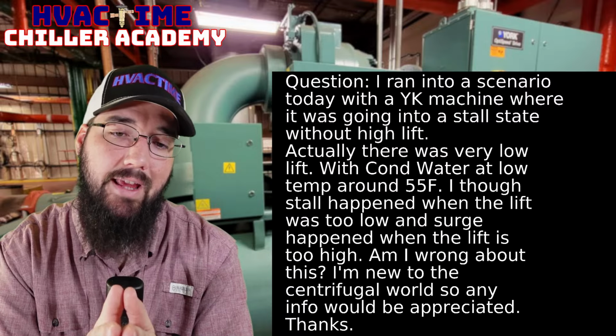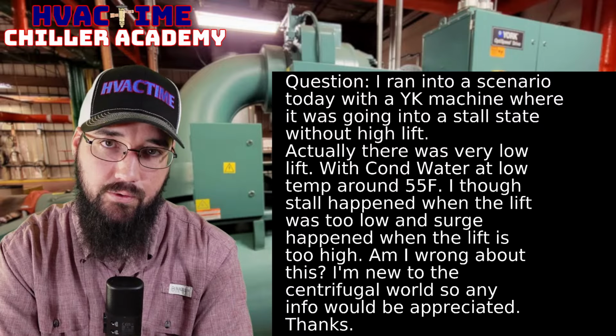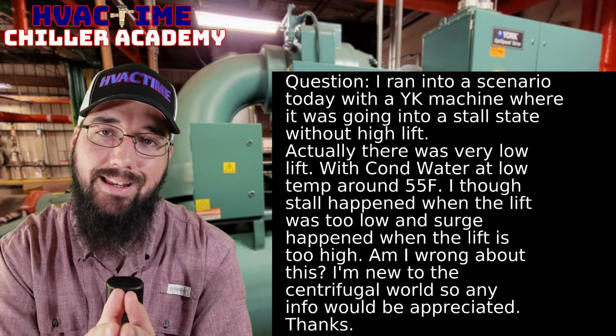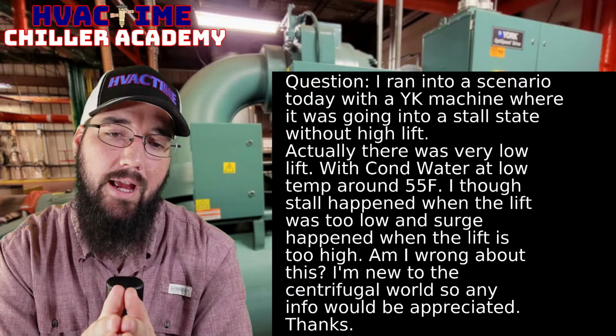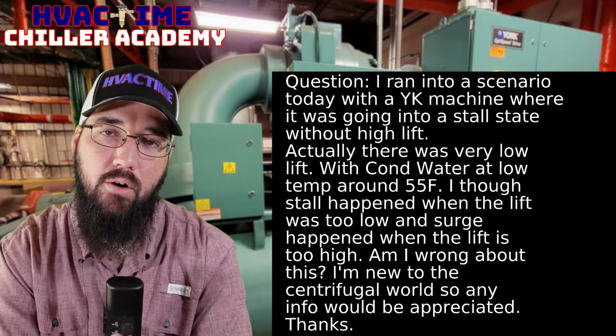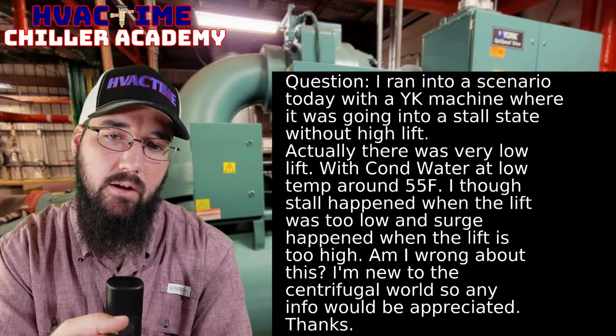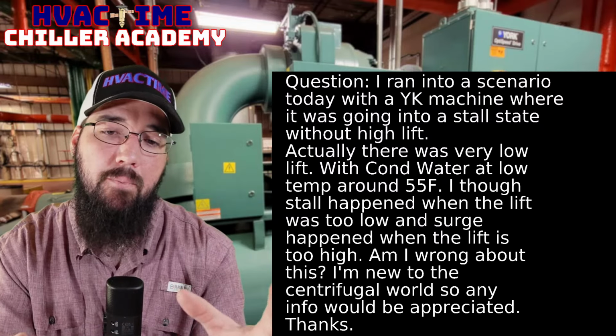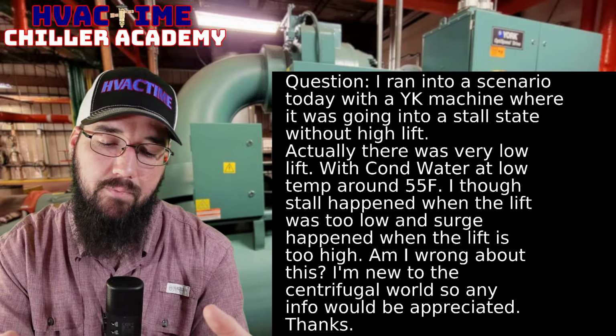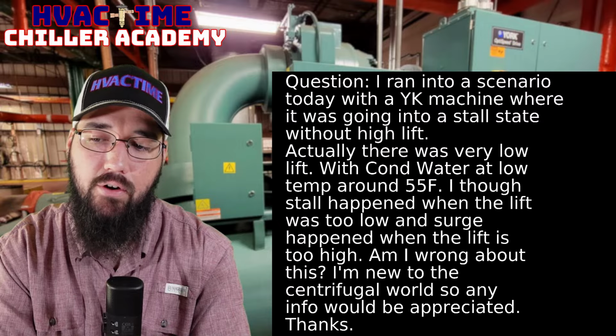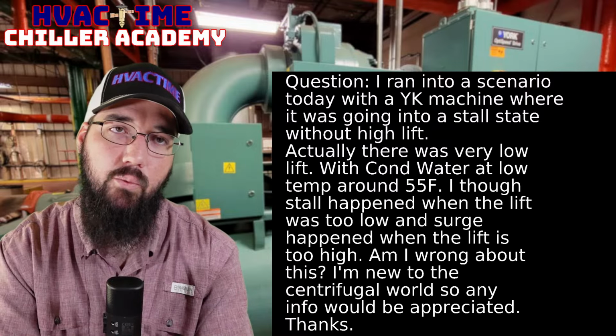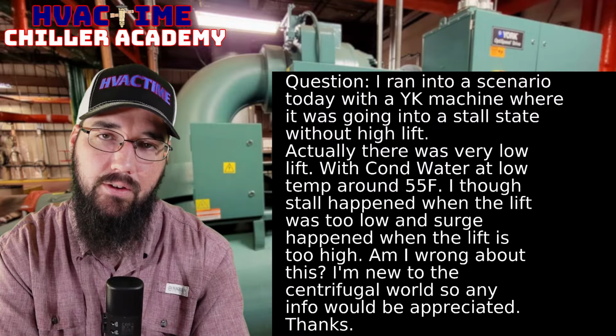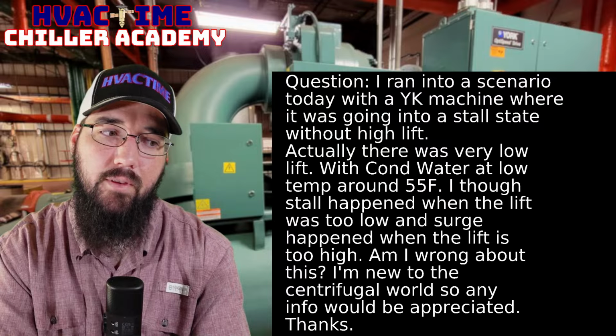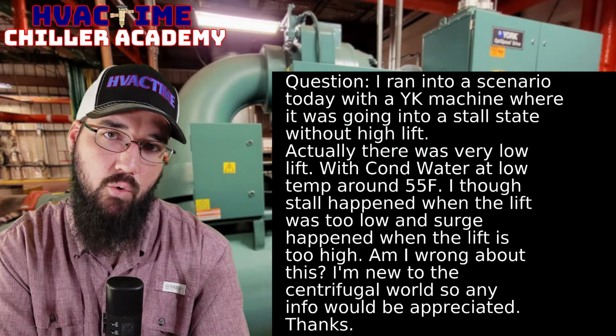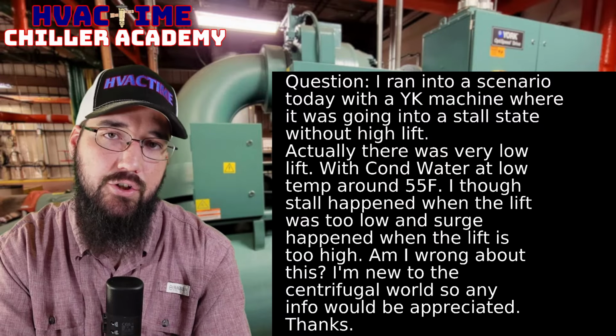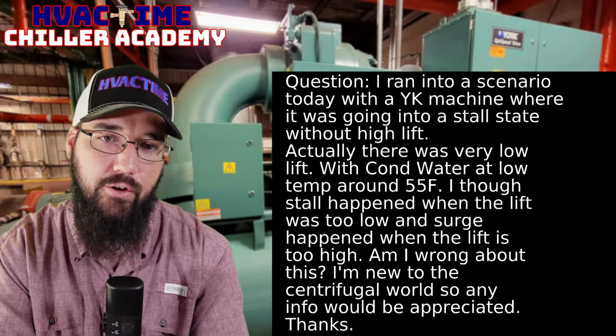But there are caveats to using those low temperatures. They can't just go there in any condition. You have to use that correctly, and that's part of what we have to be careful with, and these are oiled machines, right? Keep in mind that mag bearing machines can do this in ways that oiled machines can't, because of not having oil in the system. They heat exchange better because, again, there's no oil to interfere with heat exchange.